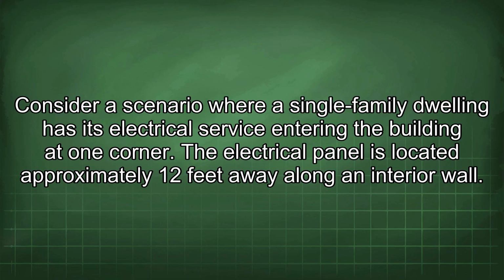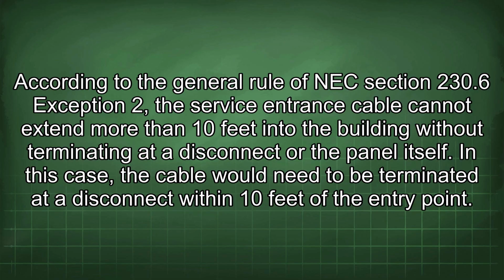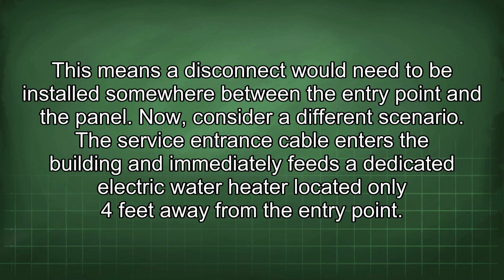Consider a scenario where a single-family dwelling has its electrical service entering the building at one corner. The electrical panel is located approximately 12 feet away along an interior wall. According to the general rule of NEC section 230.6 exception 2, the service entrance cable cannot extend more than 10 feet into the building without terminating at a disconnect or the panel itself. In this case, the cable would need to be terminated at a disconnect within 10 feet of the entry point. This means a disconnect would need to be installed somewhere between the entry point and the panel.